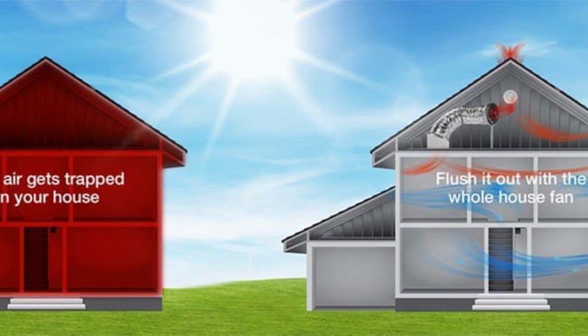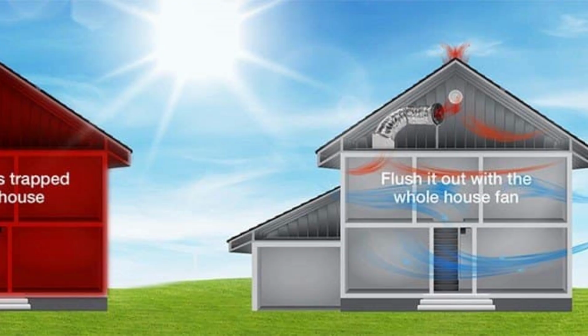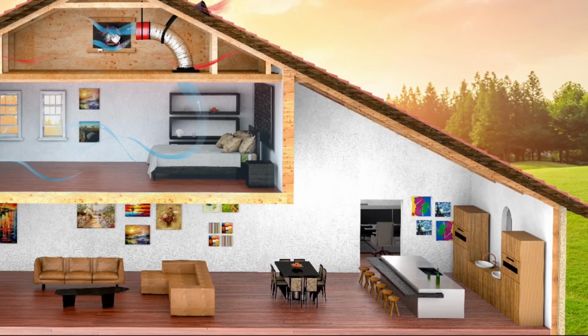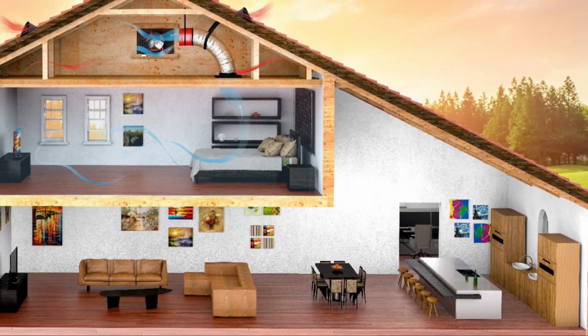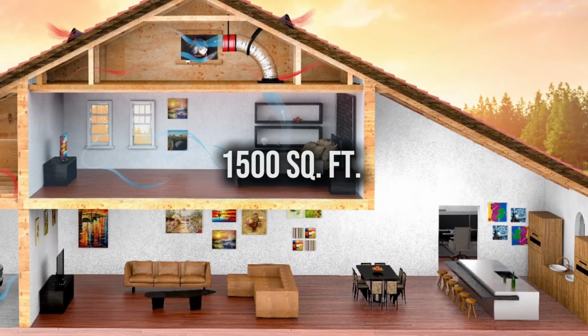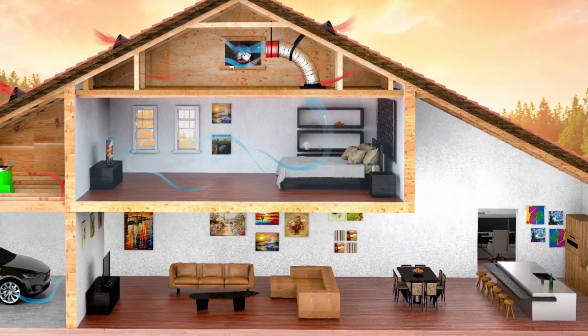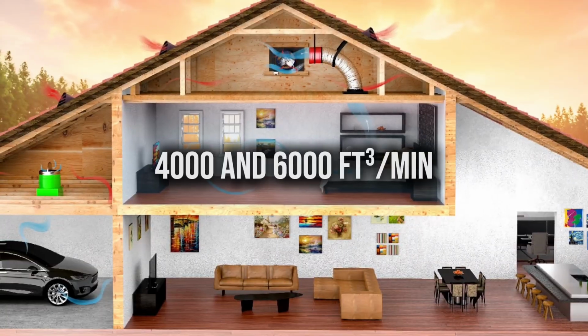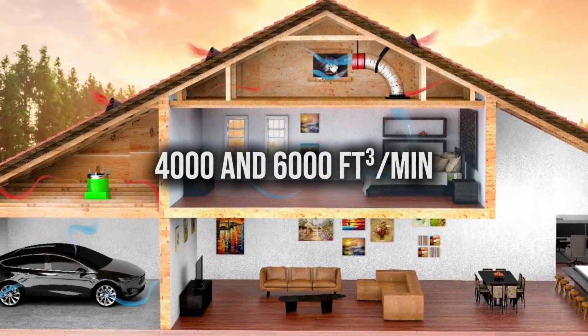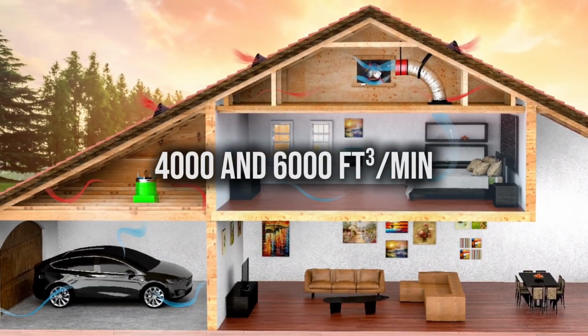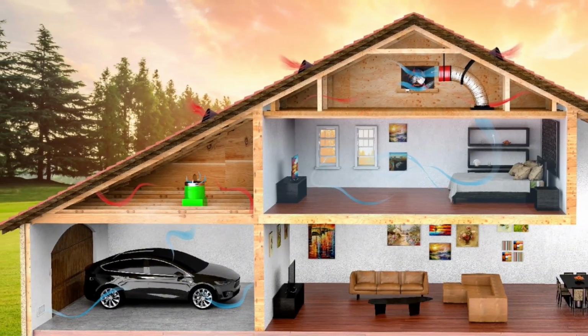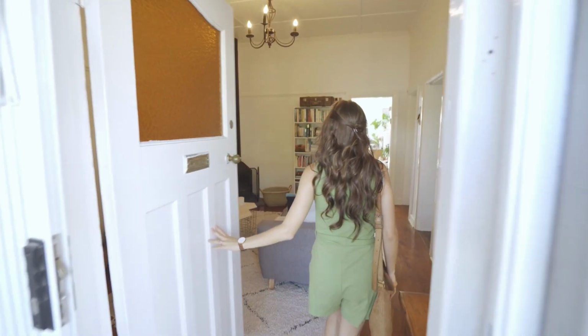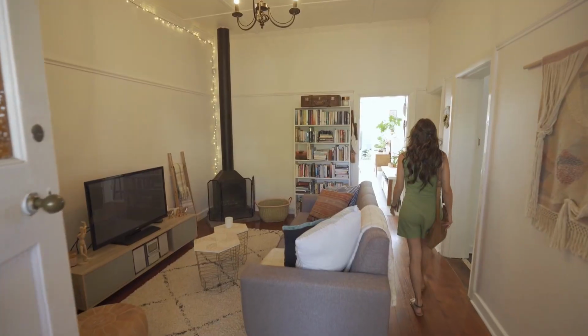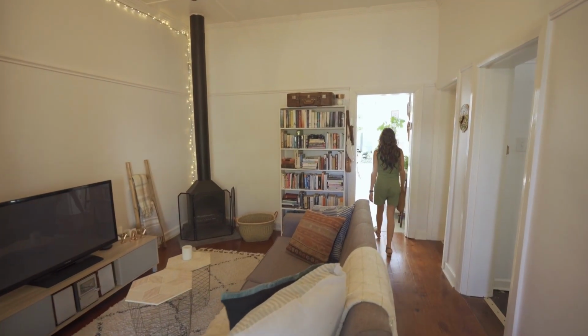What made the whole house fan genuinely remarkable was the speed of the air exchange. A properly sized unit for a 1,500 square foot home moves somewhere between 4,000 and 6,000 cubic feet of air per minute. To put that in terms you can feel, it is enough airflow to replace the entire volume of air inside your house roughly once every 3 minutes.